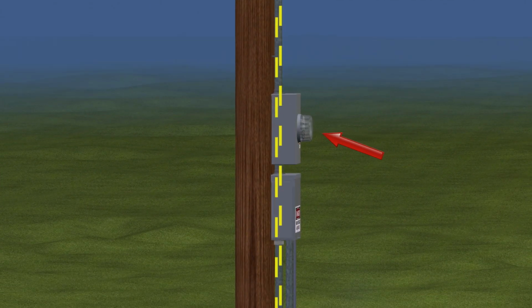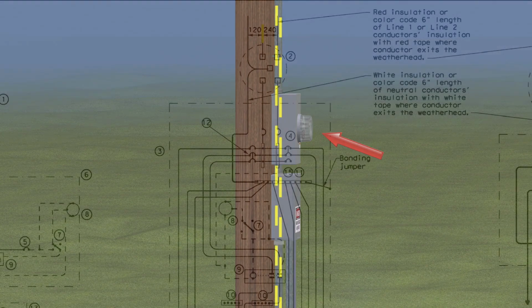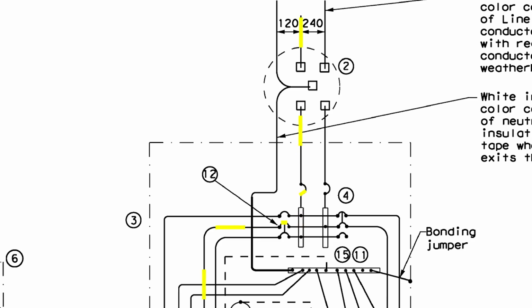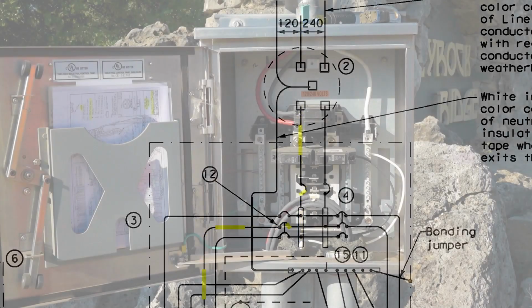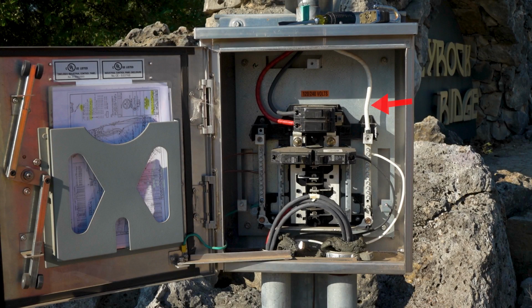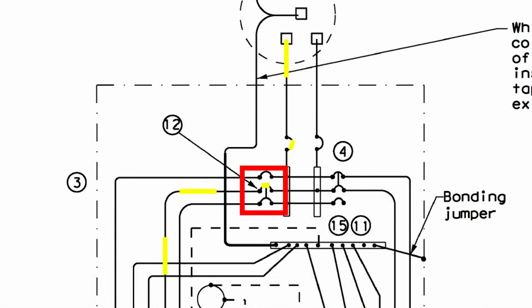The conductors then pass through the utility company's billing meter. From the meter, 2 of the 3 conductors connect to the main circuit breaker in the service enclosure. The third conductor is the grounded or neutral conductor and connects to the grounding bus bar in the service enclosure. The neutral carries any unbalanced electrical current not carried by the 2 other conductors. The grounding bus bar also provides a place for the connection of neutrals, equipment grounding conductors, and the grounding electrode conductor. Circuit breakers protect conductors from excessive current.